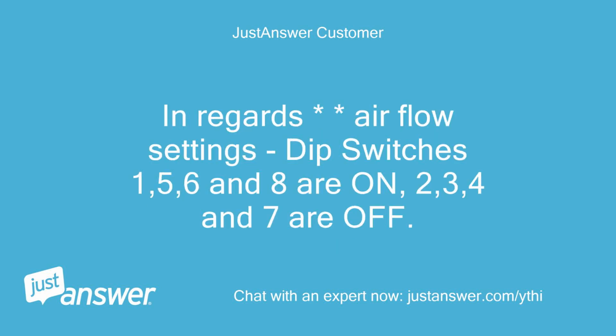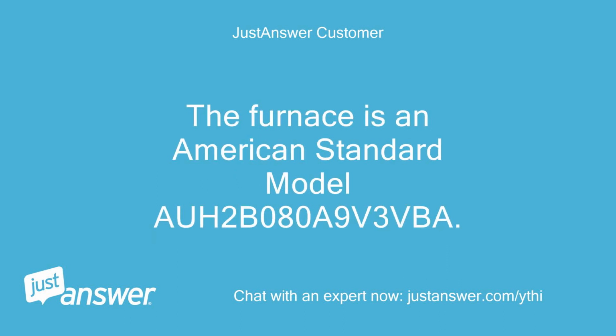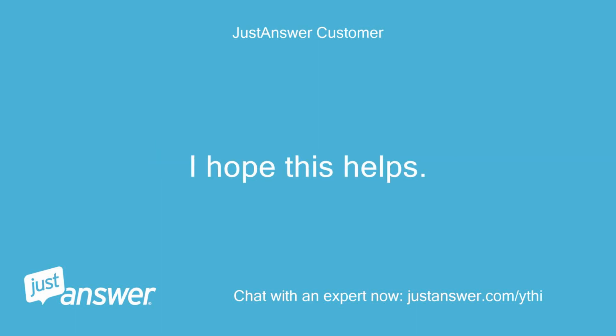In regards to airflow settings, dip switches 1, 5, 6 and 8 are on, 2, 3, 4 and 7 are off. The way I read this is normal cooling airflow for a 3-ton condensing unit, which I have, enhanced mode fan off settings and medium-low heating airflow. The furnace is an American Standard Model AUH2B080A9V3VBA. No smoking guns that I can see. I hope this helps.